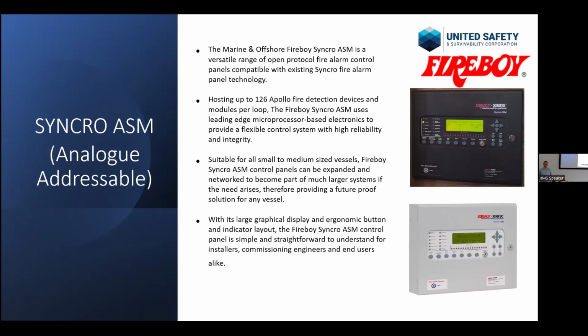So it's mostly probably used on bigger boats, pleasure boats, fishing vessels, commercial vessels, where you need the extra capability of, I don't know, holding the fire doors open or releasing them in case of a fire, or you can set certain detectors so that if they are in alarm, you can then operate the ventilation or use different programming to do stuff on the panel. It can have up to 126 detectors on each loop. It's got 2 separate sounder circuits, and you can network as many as 64 panels together to give you quite a big network of detectors.